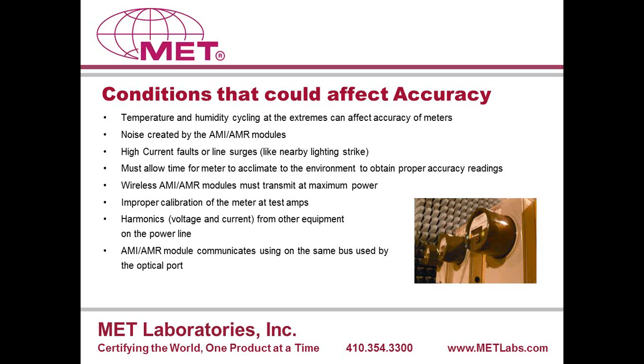Harmonics, obviously the voltage and current harmonics can affect the equipment. Harmonics are not currently part of the ANSI requirements, but they're coming down the pipeline, so they'll be in there shortly. The wireless modules, sometimes we'll see those communicating on the optical port that, most times I'd say, we use for picking up the KYZ pulses that we use to calculate the energy consumption coming from the meter product. So you have to be aware of those sorts of situations, otherwise it'll look like the accuracy is completely out of whack.